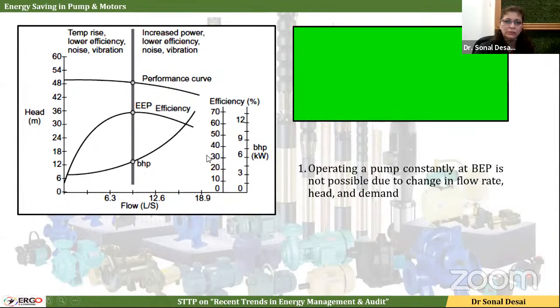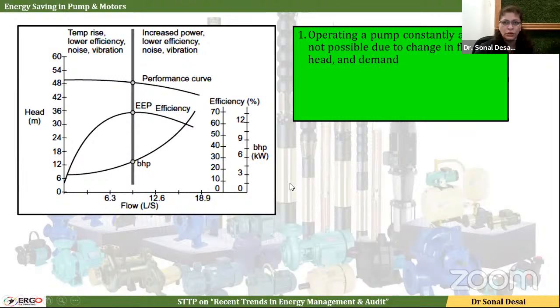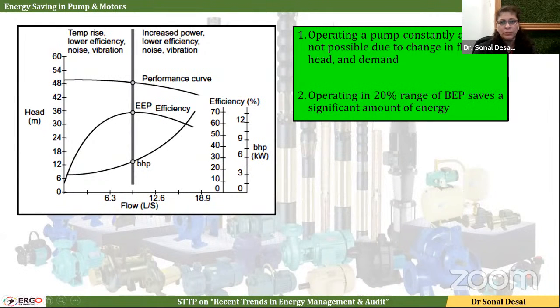So as I was talking about, from an energy performance point of view, we should make our pump operate at the best efficiency point. That is where there will be minimum power consumption and maximum efficiency achieved. So when we are operating the pump in and around BEP, it will have minimum power consumption. But it is not always possible because the flow is continuously varying, and at times the requirement is also continuously varying. It all depends on the end-to-end application.